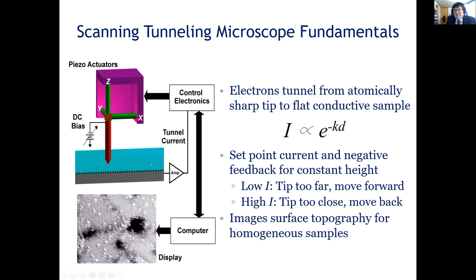So you start by taking the first one and you move in a straight line the whole way along the first row. Then you turn around and you come back along that row. So the first pass we call the trace and the second pass we call the retrace. We can compare those to confirm that our image quality is good. Once we've got the trace and retrace of the first line, then you move one pixel orthogonally to the next row and you repeat the process until you get the whole image required. We call the direction it originally starts scanning in the fast scan direction, and the orthogonal direction the slow scan direction, because for a 1000 by 1000 pixel image, it takes 1,000 times longer to move in the slow scan direction than the fast scan direction.